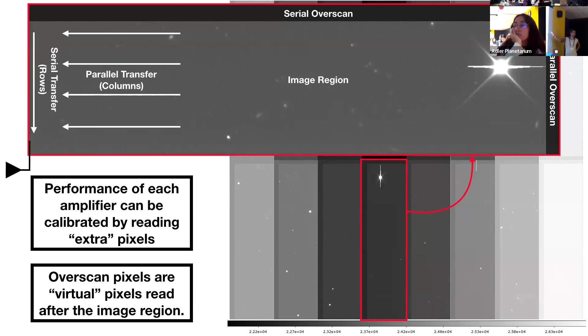Oh, yeah. So if it's 16 wide on your CCD, but when you look at what you got, it'd be like 20 instead, because you have extra rows. Right, so yeah, if the physical dimension of the CCD is 4,000 pixels, when you read out these extra pixels, the size of the image that you would get would be bigger than 4,000 pixels. You haven't expanded the physical size of your CCD or anything like that. You're just adding extra pixels onto the end, and that's why it appears discontinuous. This is one of the main things when you look at raw images, you're like, what is going on here? Right?